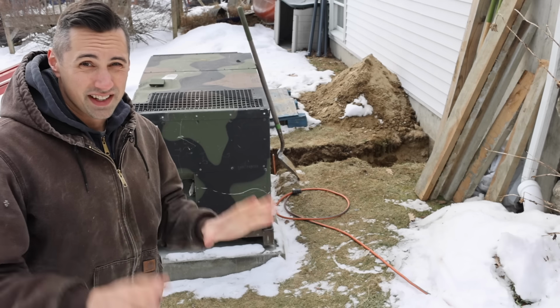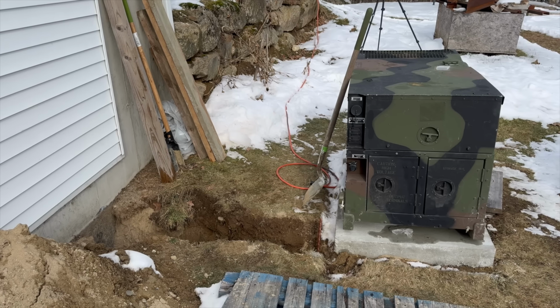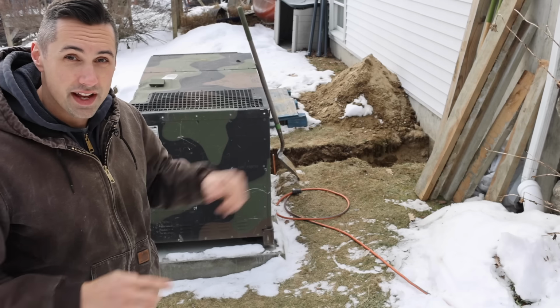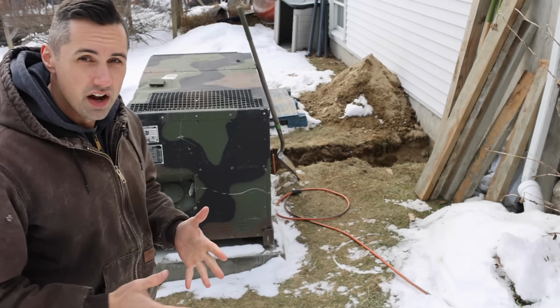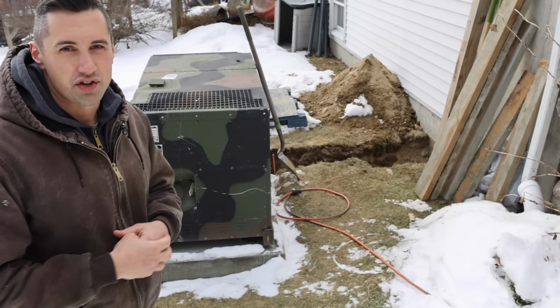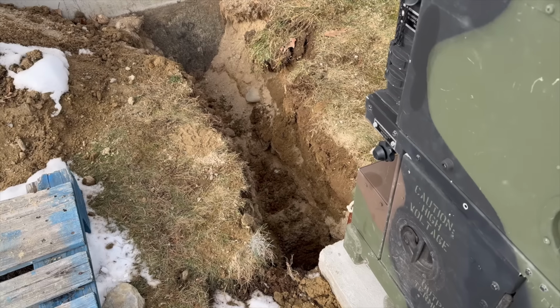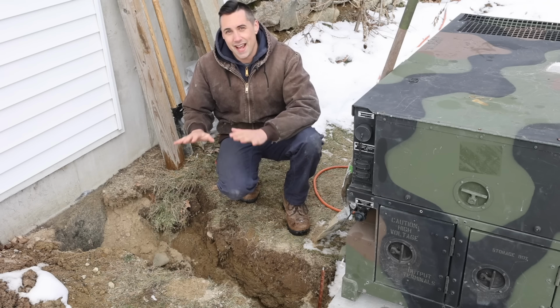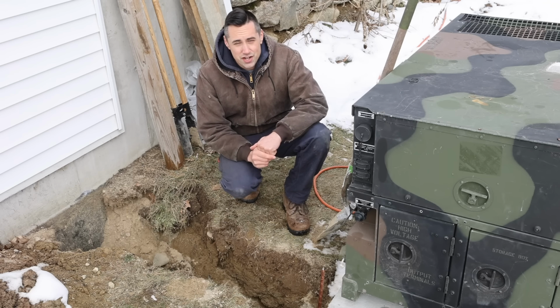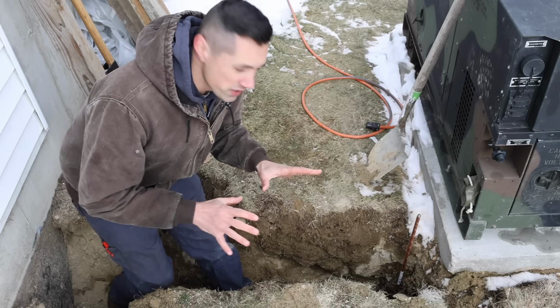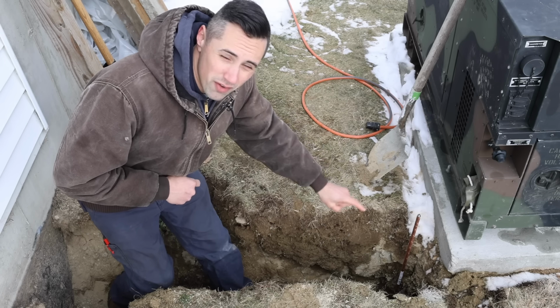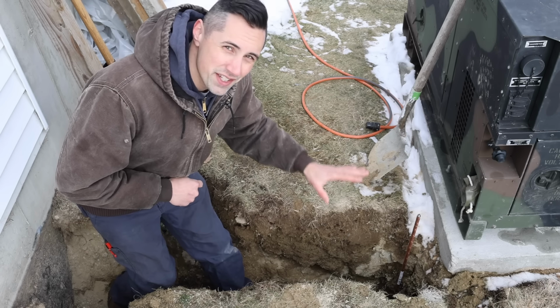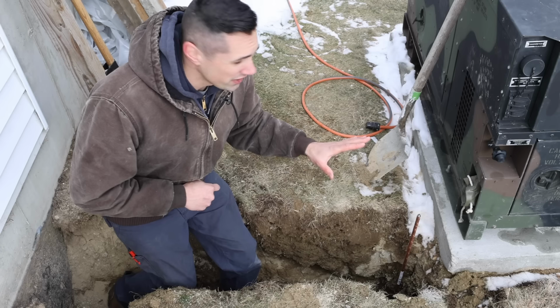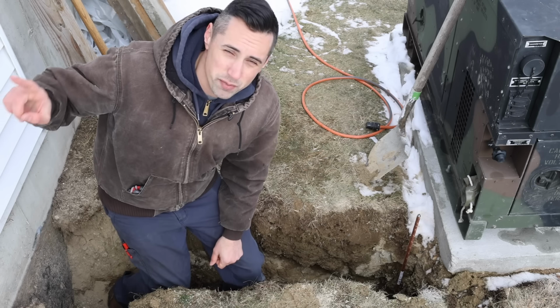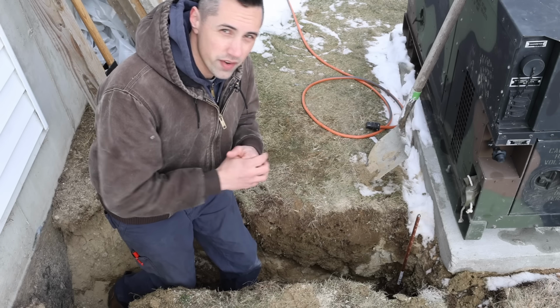My first installation note is that the generator needs to be at least 5 feet away from the house, so that if the generator catches on fire, hopefully the house won't also catch on fire. Second, I've dug a trench that'll allow me to run conduit from the house to the generator at a depth of at least 18 inches as required by the National Electric Code. I also have a quick note about this ground rod, which I drove 8 feet into the ground. It's not technically required for this installation because the generator is grounded to my house all the time through my transfer switch.